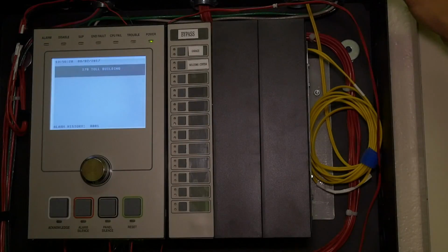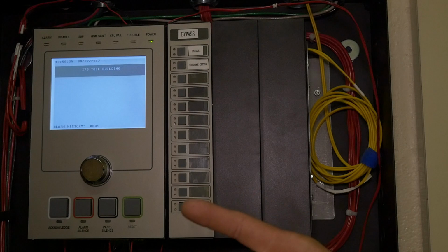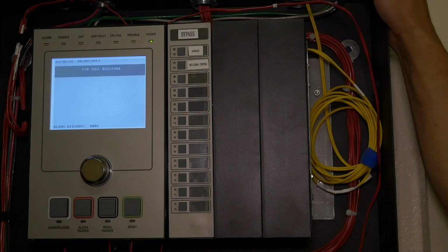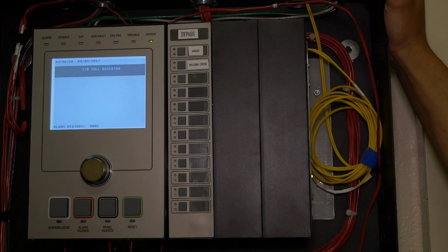Because the way this panel works is, say that a detector goes off and we hit alarm silence and panel silence, and then a new detector goes off, it's going to set the alarms off. So you're still covered if they let one go that they know about until we can get someone in to service it. Everything else is still going to function the way it needs to. Right. That's what I meant to say. Yep, no, that's good.